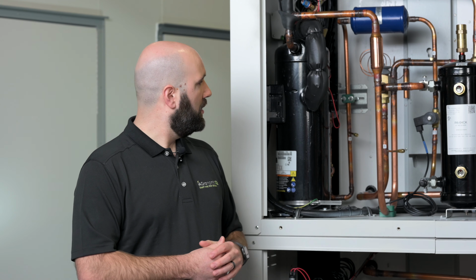In this case, we've got a Copeland ZPS two-stage compressor. This is a 20-ton unit. This is the largest unit today that we build with these two-stage compressors. Anything larger than this would be built with a Bitzer scroll paired with an inverter.